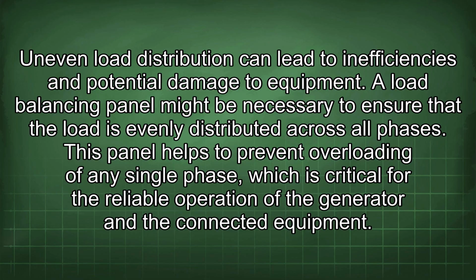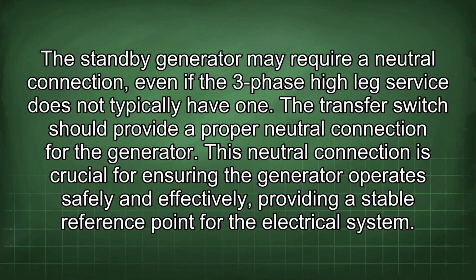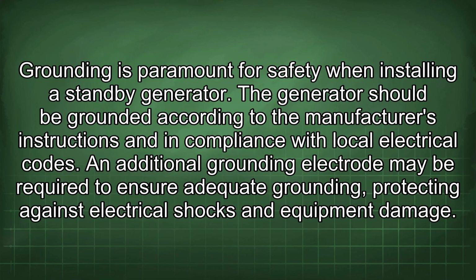and the connected equipment. The standby generator may require a neutral connection, even if the three-phase high-leg service does not typically have one. The transfer switch should provide a proper neutral connection for the generator. This neutral connection is crucial for ensuring the generator operates safely and effectively, providing a stable reference point for the electrical system. Grounding is paramount for safety when installing a standby generator.